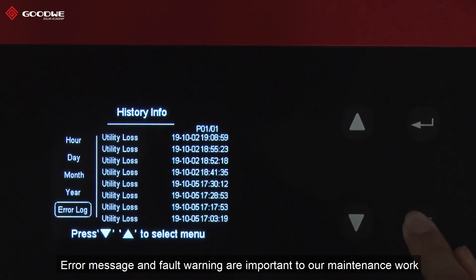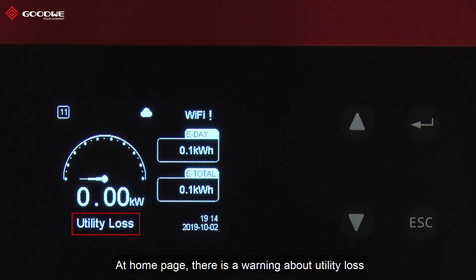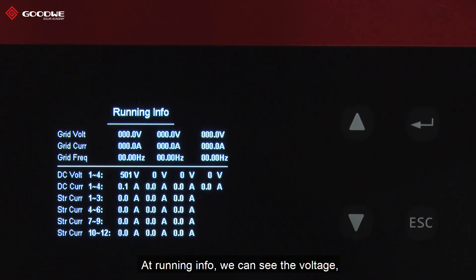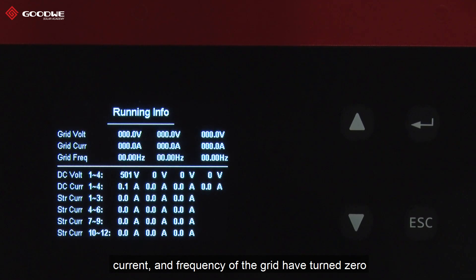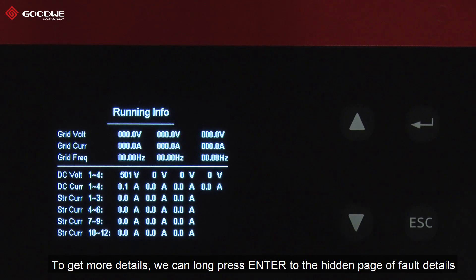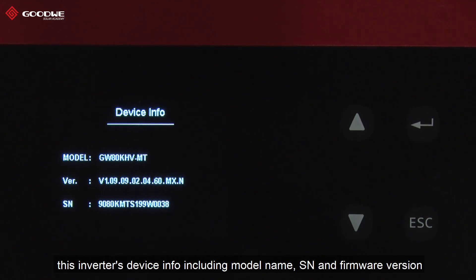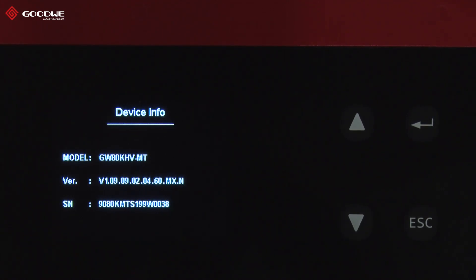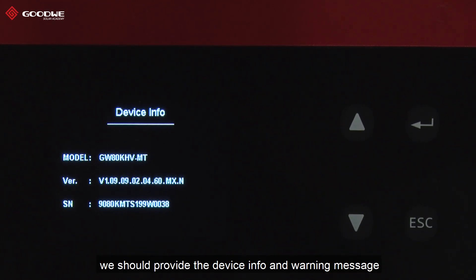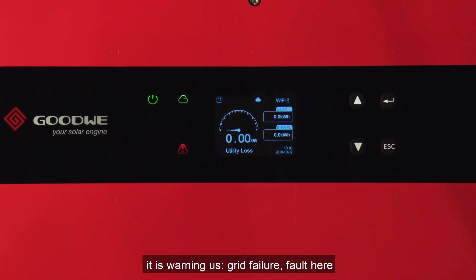Error messages and fault warnings are important to our maintenance work, and there are many ways to get informed. On the homepage, there is a warning about utility loss. In Running Info, we can see the voltage, current, and frequency of the grid have dropped to zero, while there is still DC input — indicating PV energy is present but the grid has failed. We can press Enter to access the fault detail page for more information. From the last menu, we can note the inverter's device info including model name, serial number, and firmware version. To get swift recovery, we should provide the device info and warning message to our maintenance team or GoodWe. In addition, when the red fault indicator is on and the green run indicator is dark, it is warning us of a critical failure fault.